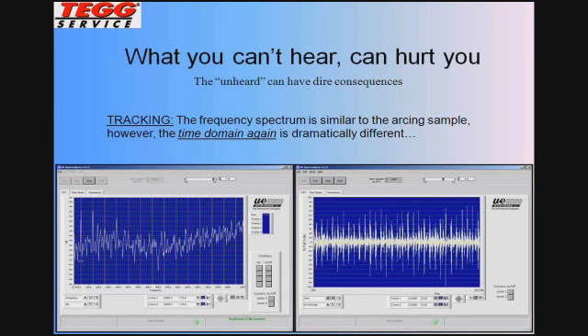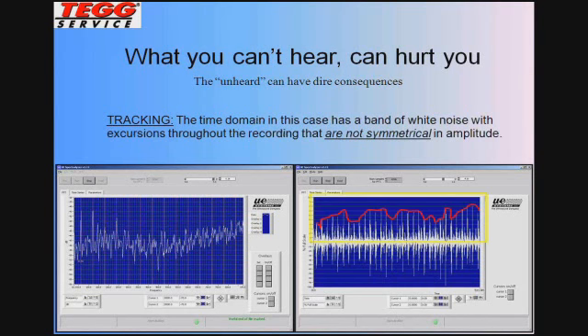If you recall on the arcing, we had the broad band of white noise, and we had the full intensity discharges with no real rhyme or reason that occurred throughout the recording. On the tracking, we have the same broad band of white noise, but we have many excursions here that are more frequent in this case than the arcing was. The key thing here is we have the multiple excursions all the way across there, but you have varying levels of intensity or amplitude. This is one of the things I look for in tracking, is no consistency in the amplitude on the excursions.